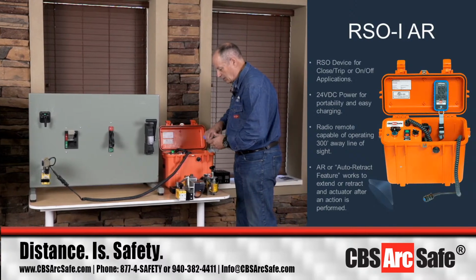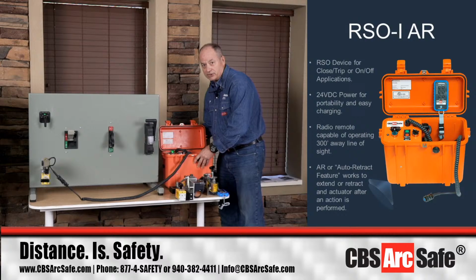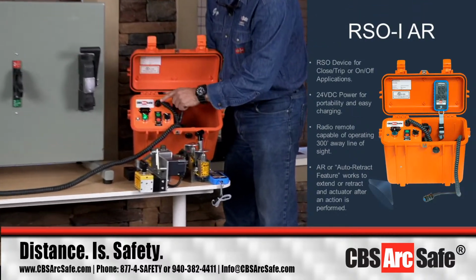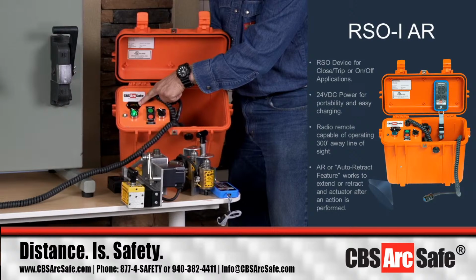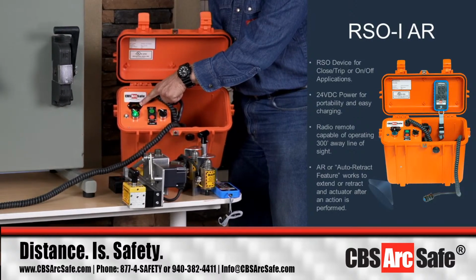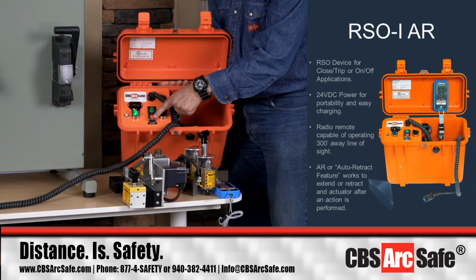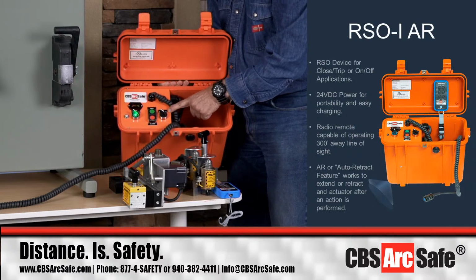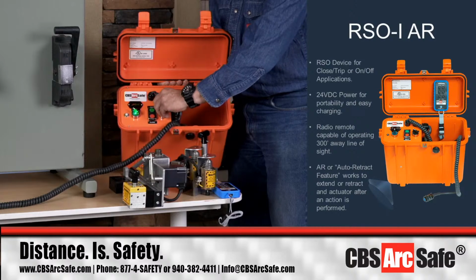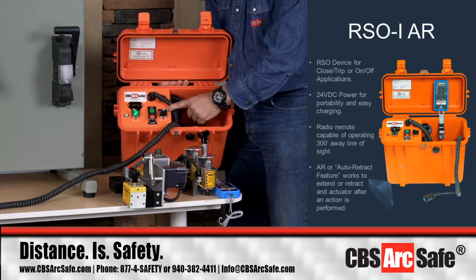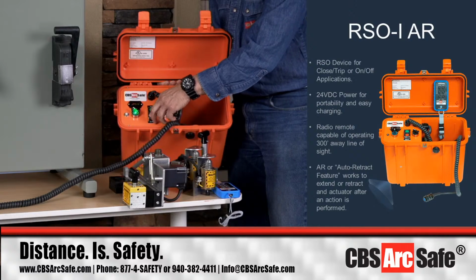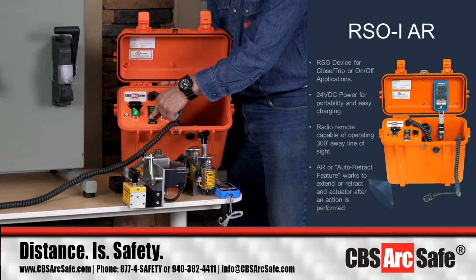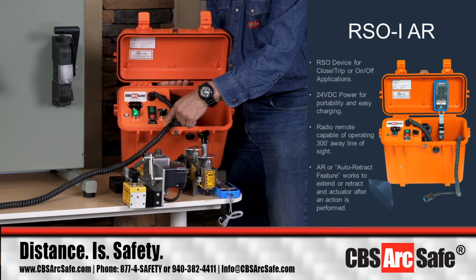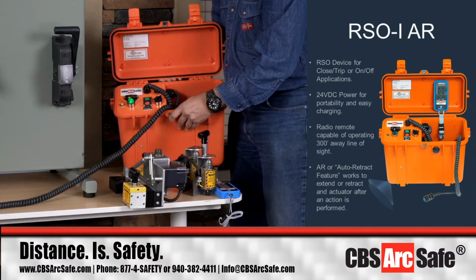So looking at the RSO-I, I'm going to tilt the box here for a second to show what it shows here. You've got the power switch, you've got the LED which indicates our battery strength. Three bars, or three green lights, indicates 24 volts in the system. You've got your trip and your close, and then you have your AR switch functionality. For the RSO-I AR, we're going to switch the functionality to the on position. And now when we go to push the button and operate the actuator, it operates, and then when we release it, it automatically retracts. That's what AR functionality is.